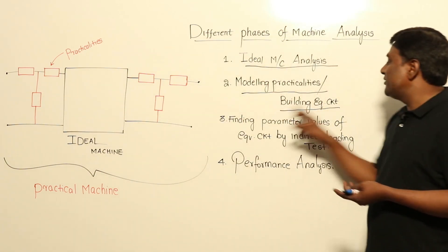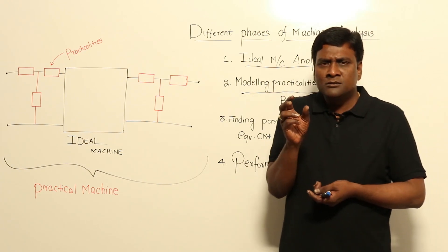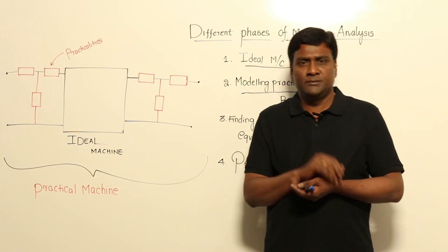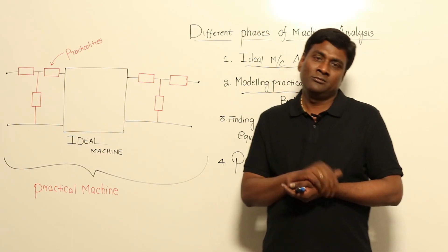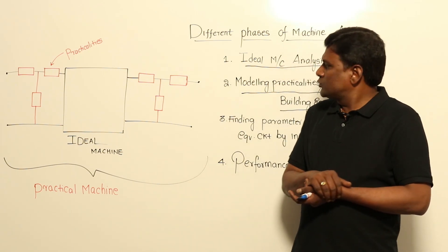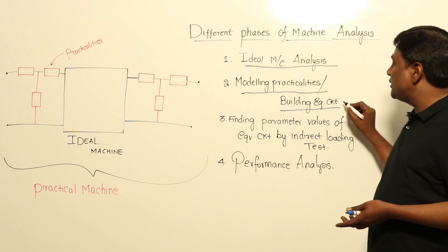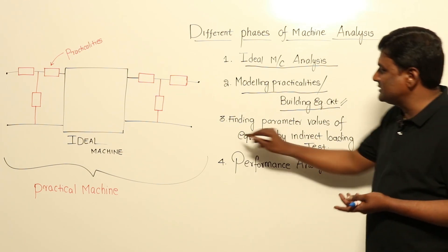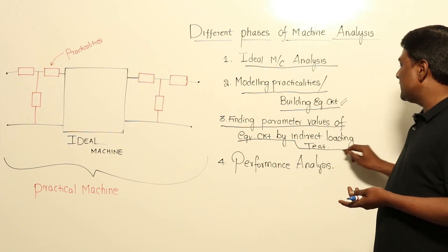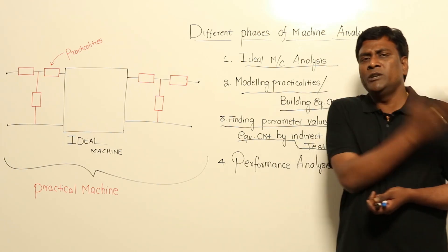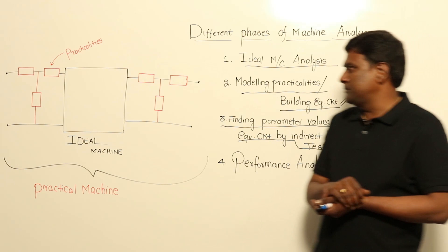Once the practicalities are modeled — finding the equivalent circuit — leakage can be modeled as inductance, copper losses as resistance, and core losses as resistance. Once modeling is over, the third phase is finding the parameter values of the equivalent circuit by indirect loading tests. We decided not to go with direct loading tests, so in an indirect way we have to find the parameter values.